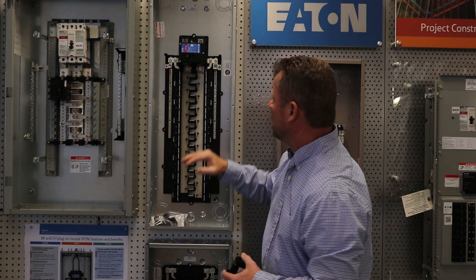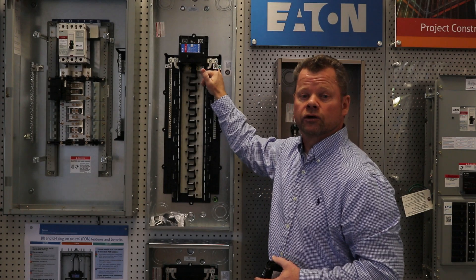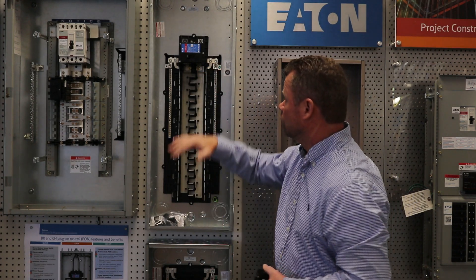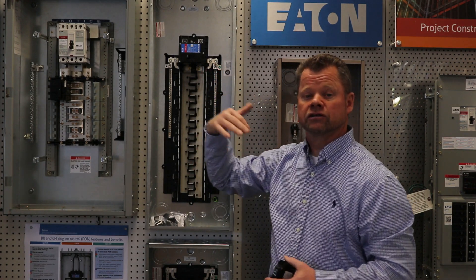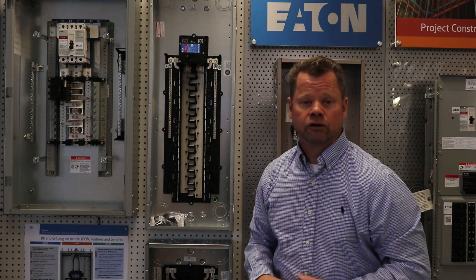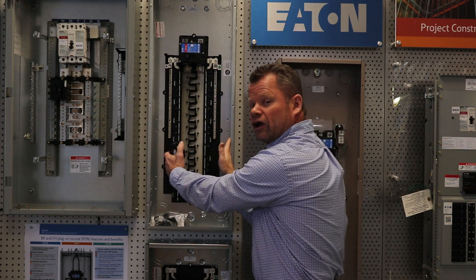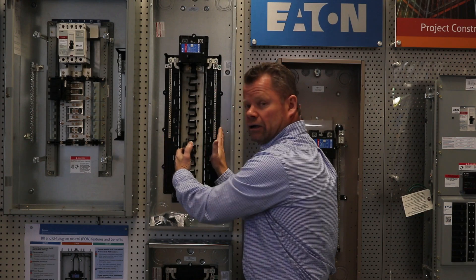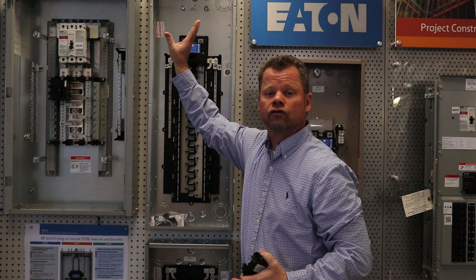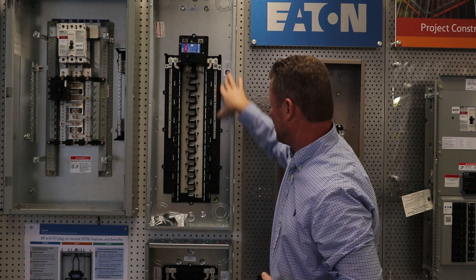Another main feature that we have here is the bonding screw. It's already in place, ready to be inserted when ready. If you don't need the bonding screw — for example, in a sub-panel application — you can just remove the bonding screw and you're good to go.